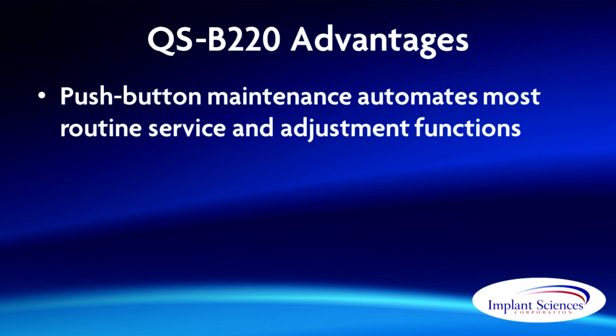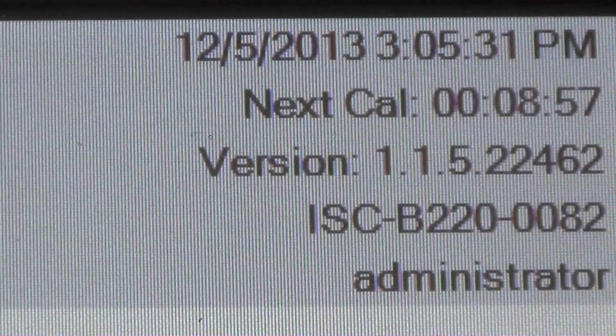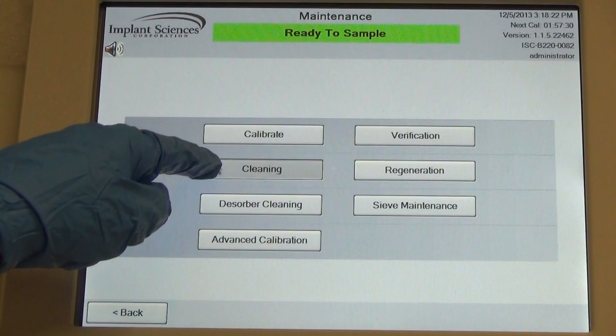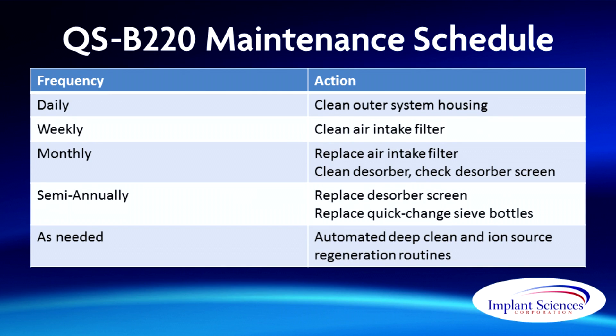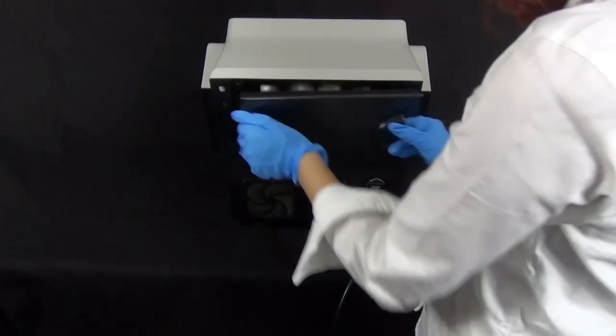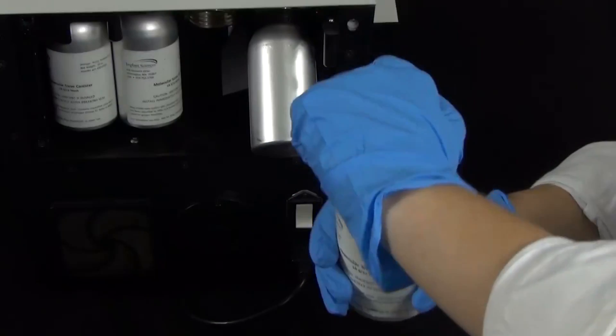The QS-B220 automates most routine maintenance and adjustment functions. In-Cal, Implant Sciences' patented automatic internal calibration system, optimizes performance without operator intervention and without the use of expensive consumable supplies. Push-button maintenance allows authorized users to conduct routine service operations such as system cleaning with just a few touches. There are no internal service items on the QS-B220. Thanks to the system's long-life dopants and calibrants, the only customer-replaceable parts are easily accessed filters and the system's innovative quick-change sieve bottles. The sieve bottles last for months, and when they need changing, the process takes just a moment or two and can be done without turning the system off.